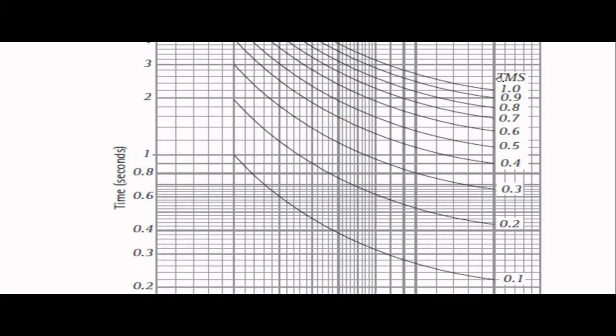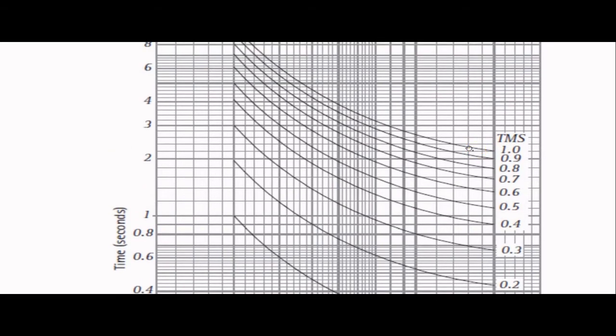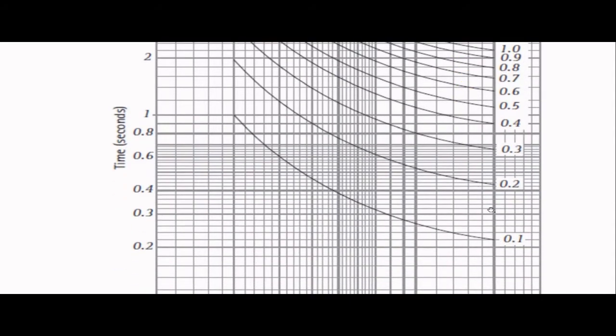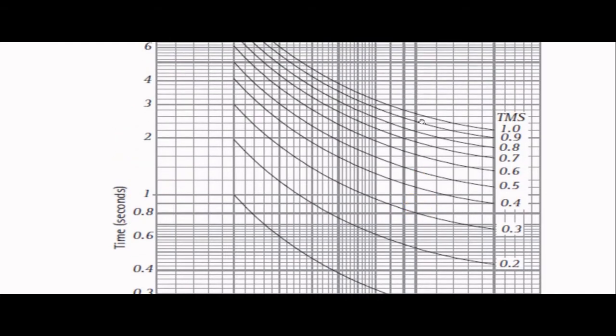So here you see a total of 10 curves. This is curve number 1 and this is curve number 10. Each curve represents a particular time multiplier setting. In the electromechanical relay there is one dial to set the relay operating time, which is nothing but the time multiplier setting. If the time multiplier setting is fixed at 1.0, we follow the first curve. If it is fixed at 0.9, we follow the second one. Similarly, if it is fixed at 0.1, we follow the last one. So that's why a total of 10 curves are there.